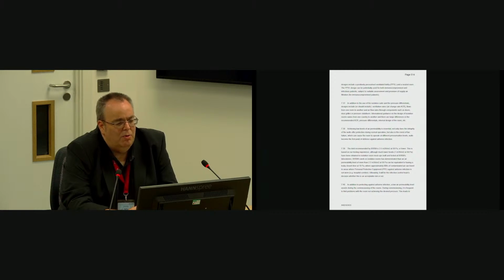And indeed, we recommend within the HBN that for the PPVL room to have the best resilience in use, we should not be putting any form of filtration on the exhaust air, because that will introduce a system resistance that in the event of an extract fan failure would interfere with the open air path to outside.